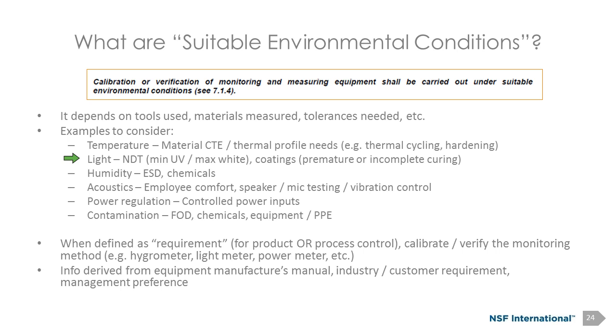Likewise, if I'm doing some verification efforts in the sound arena, ambient noise or vibrations may be impactful to the calibration or verification effort. In some cases, that material coefficient of thermal expansion is going to play a role, depending on the type of tool, the type of measurements, the tolerances. So we need to ensure that we understand the capability of those tools, maybe as they're measuring a heated part that's coming out of a HIP furnace or a heat treat furnace, right?